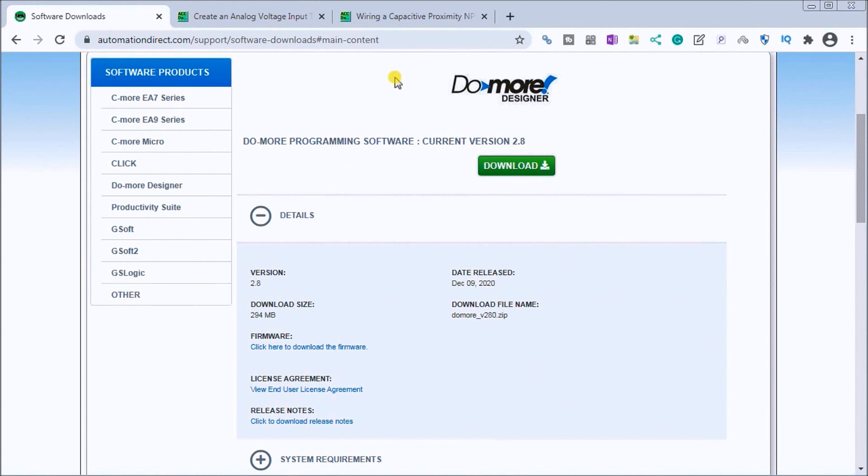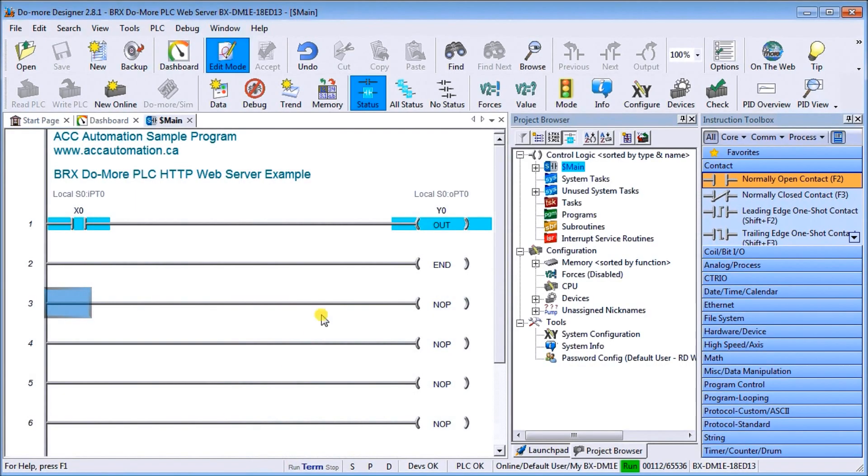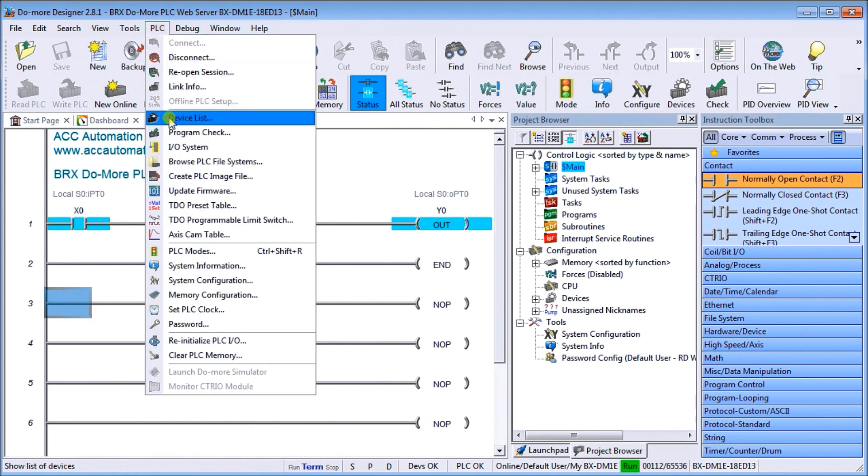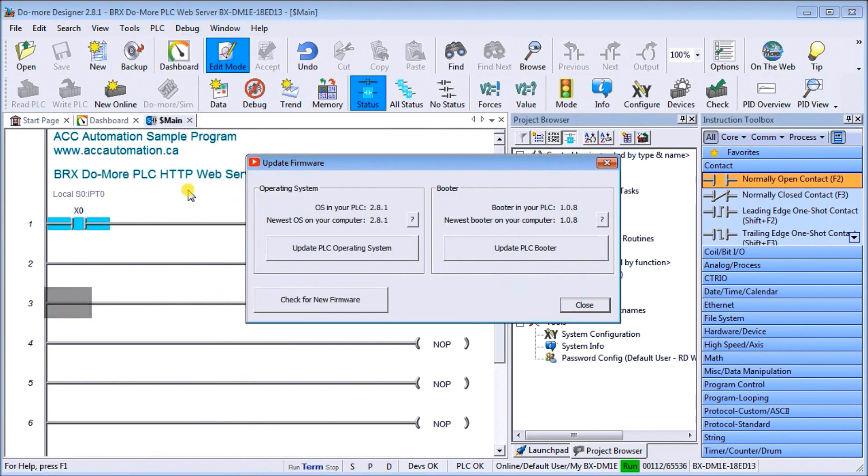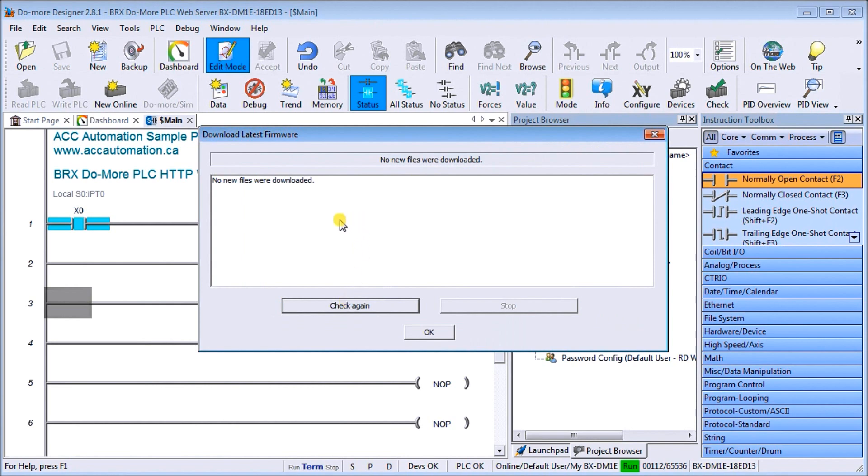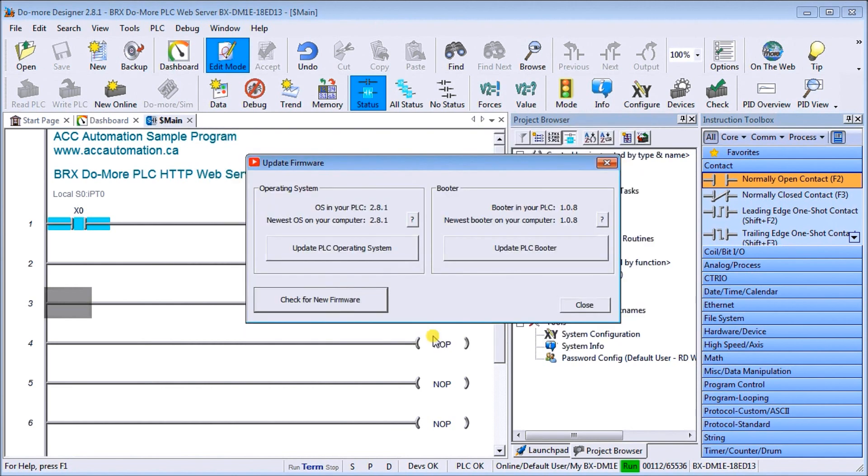Once we have that downloaded, we can call up our software and under firmware, we have to make sure that our actual hardware itself has the same firmware on it. We go PLC, update firmware, and you can see here that I have 2.81 for our operating system and our booter, we have 1.08. So these are the latest ones. We can just check if you want and there's no new files.